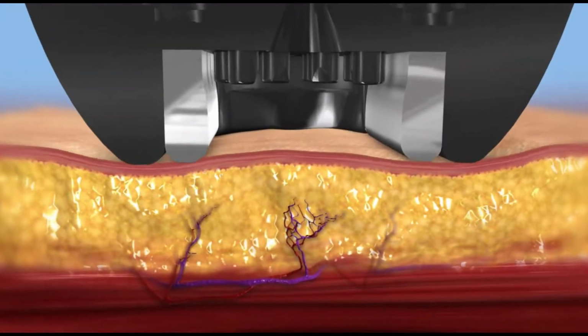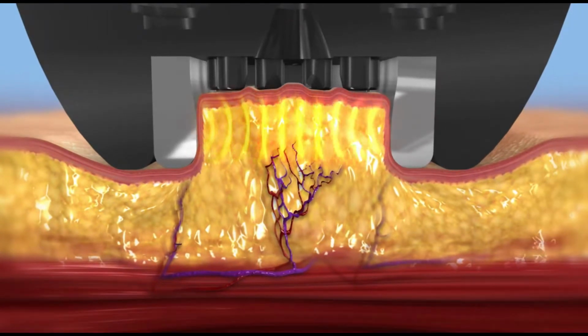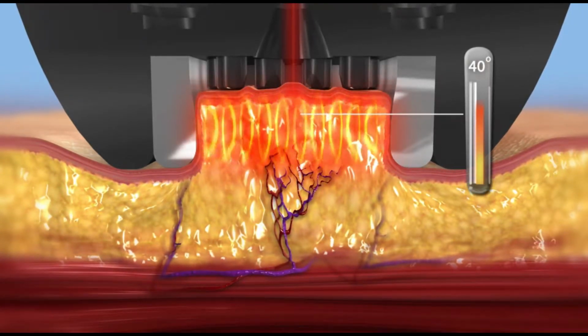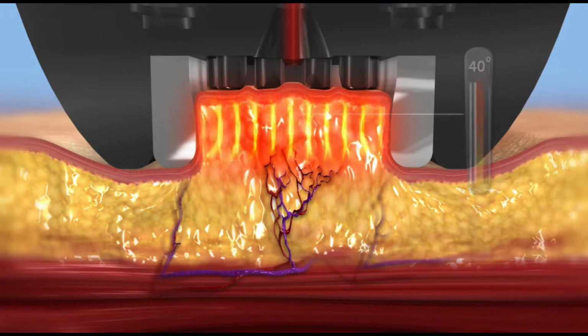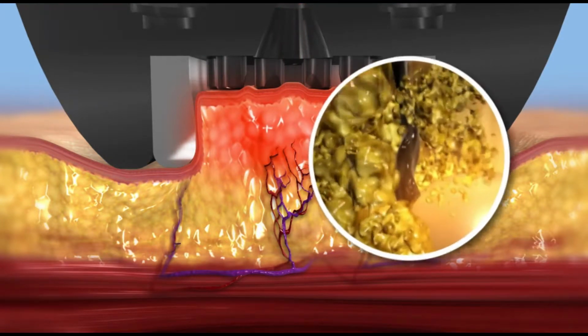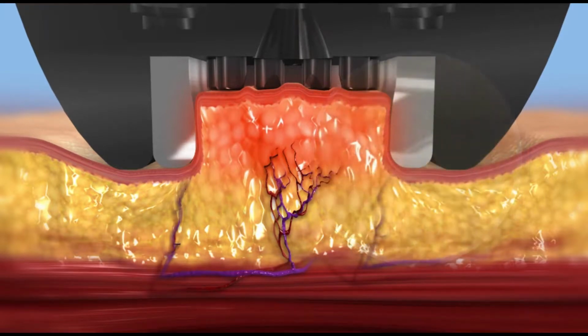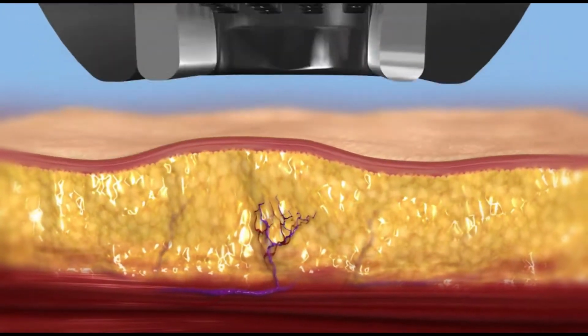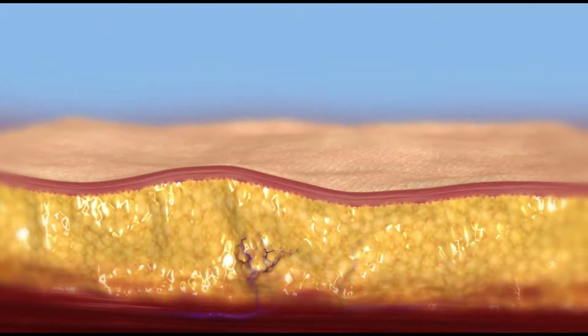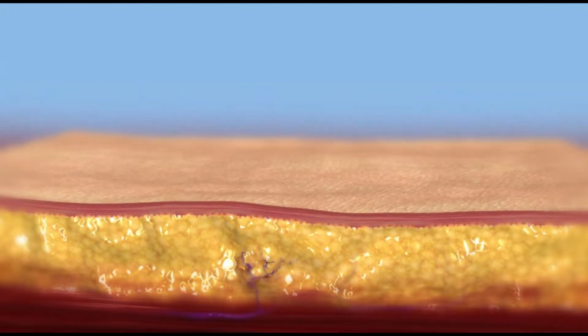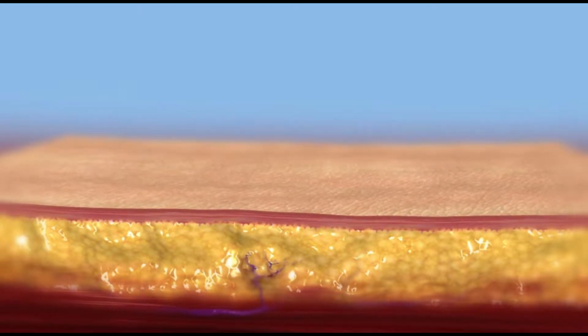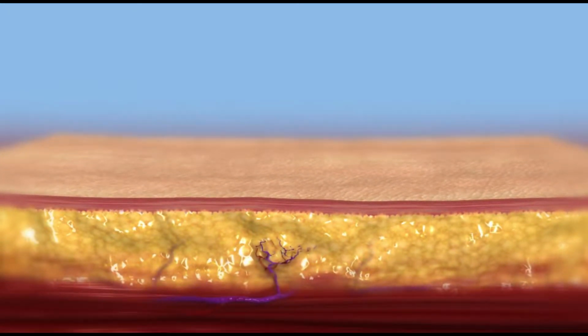The TiteFx is a suction-coupled bipolar RF system, sucking the fat into the chamber, heating that fat and dermis with basic radiofrequency energy. When it reaches the therapeutic endpoint, 42-43 degrees, high voltage electrical pulses are emitted. These create an electroporation, irreversible transmembrane damage, and an apoptotic death of adipose tissue, which then contours and remodels after a series of treatments. There's a 15% increase in collagen and up to 30% apoptotic adipocyte, non-necrotic cell death.